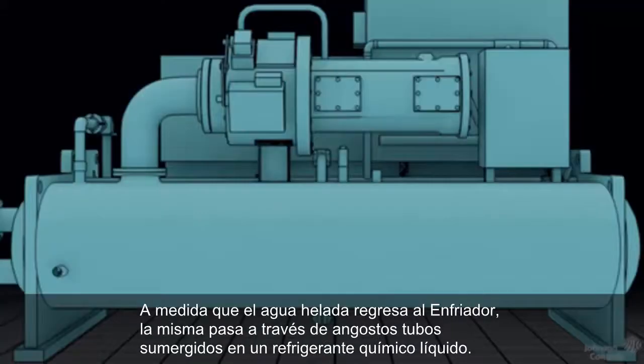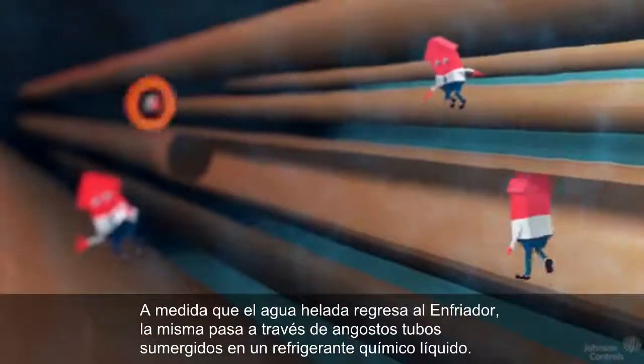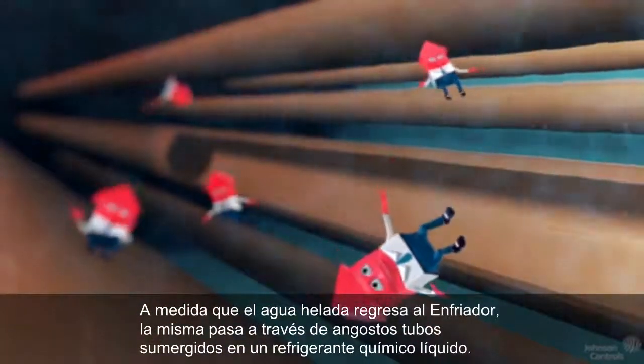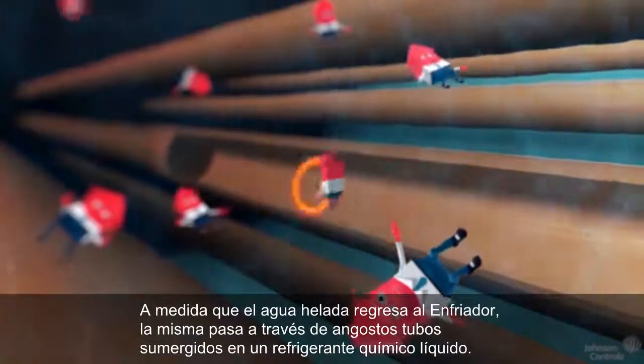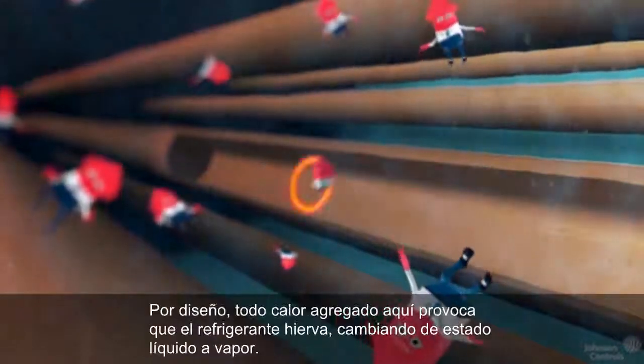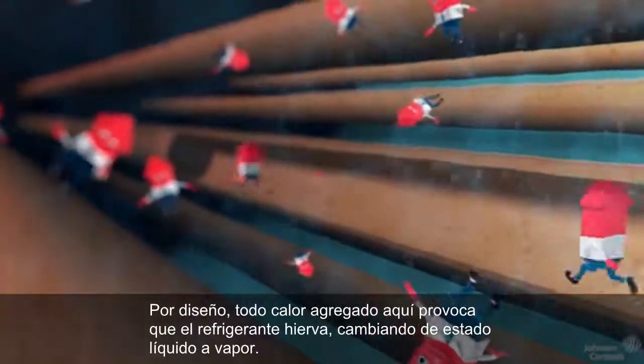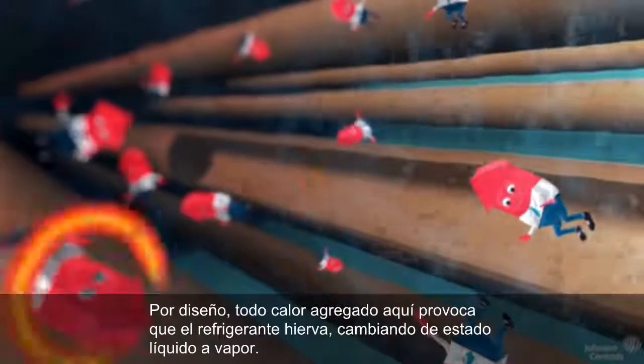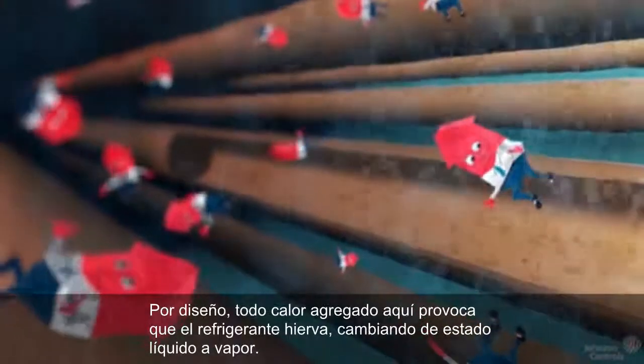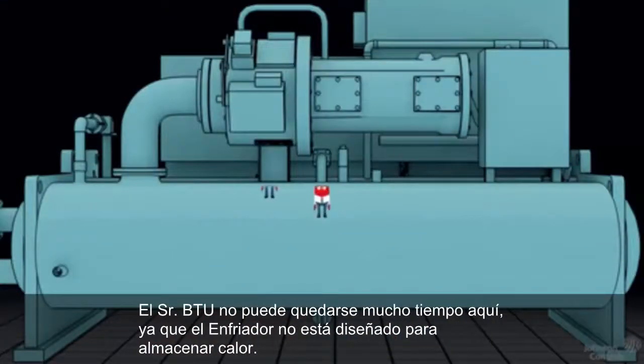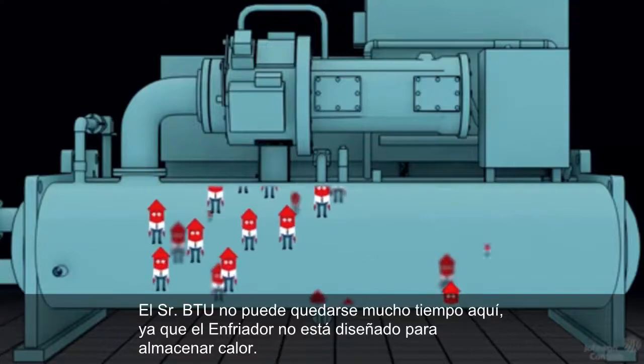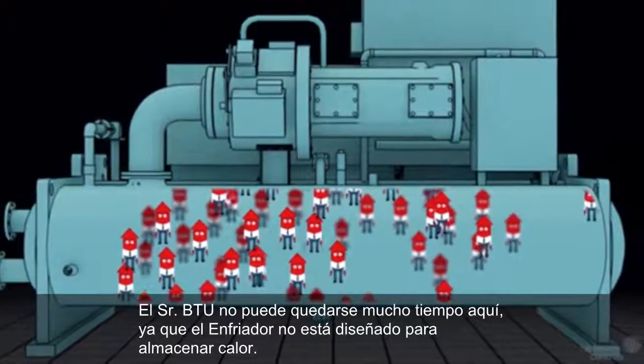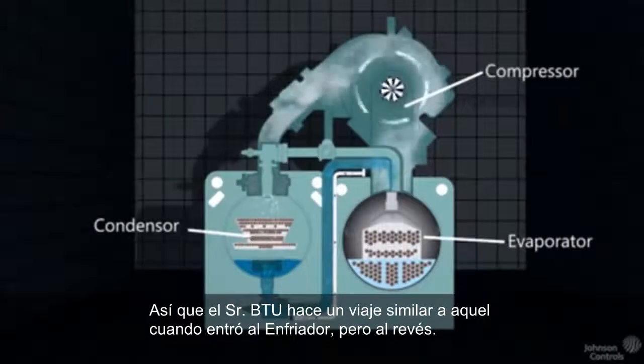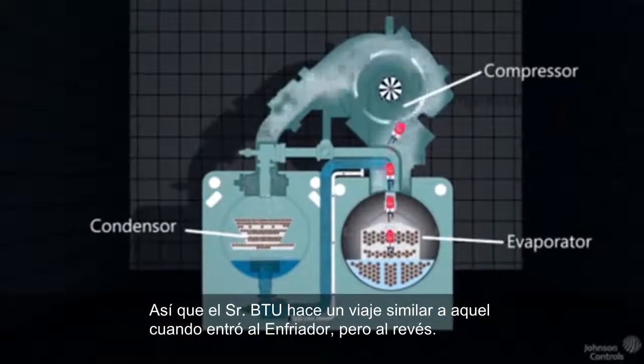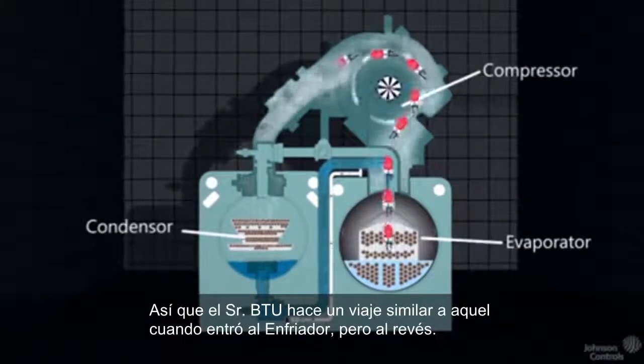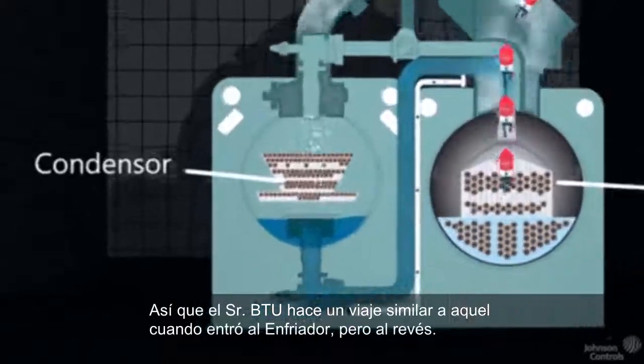As the chilled water returns to the chiller, it passes through narrow tubes that are submerged in a liquid chemical refrigerant. By design, any heat added here will cause this refrigerant to boil, changing state from a liquid into a gas. Mr. BTU can't hang around here long though, as a chiller is not designed to store heat energy. So, Mr. BTU makes a trip similar to the one where he entered the chiller, in reverse.